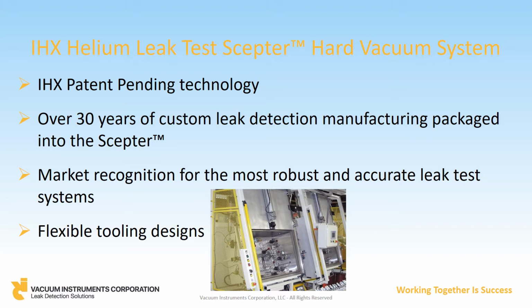The Scepter is a complete hard vacuum test system specifically designed for thermal leak detection applications. The Scepter utilizes standard components like the chamber and frame, VIC's MD490M industrial leak detector, chamber evacuation pump package, gas handling cabinets, electrical package including controls and operator interface, and a chamber-mounted calibrated gas leak, all packaged together, offering a leak detection solution to meet the most demanding thermal application testing needs. Custom tooling is supplied with the Scepter that links your product to the system. The tooling features ergonomic designs that allow interchangeability between the pallets for speed and ease of product tooling changeovers.